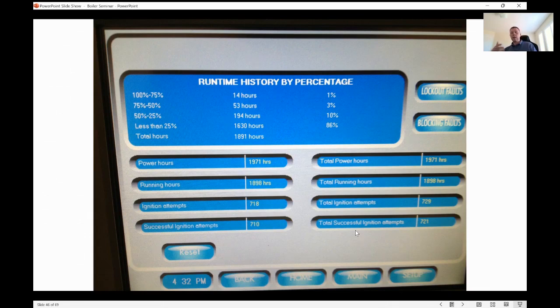Where, let's say you had a 5-to-1 turn down ratio boiler that only modulated from 20, or we'll call it 4-to-1, from 25 to 100% fire. Well, what would happen? If that system needed one boiler at 10%, well, the 5-to-1 turn down ratio boiler would turn on. It'd have more BTUs than the system needed. So it would overshoot that set point temperature because it only needs X amount of BTUs and we're giving it a lot more.